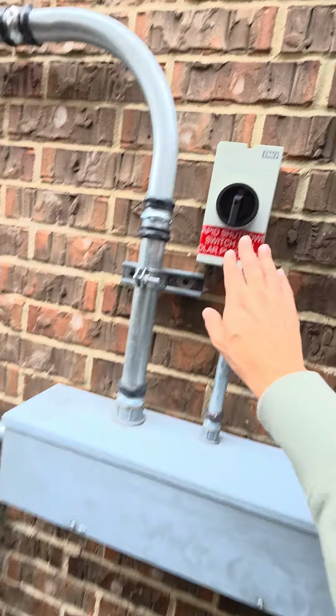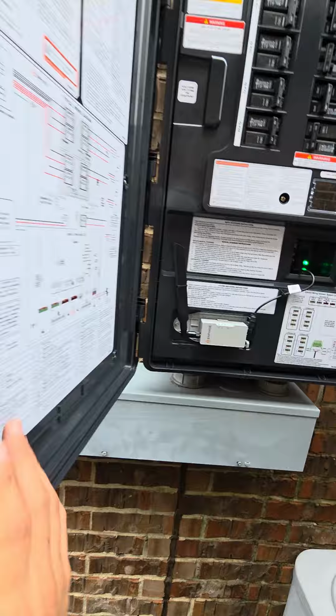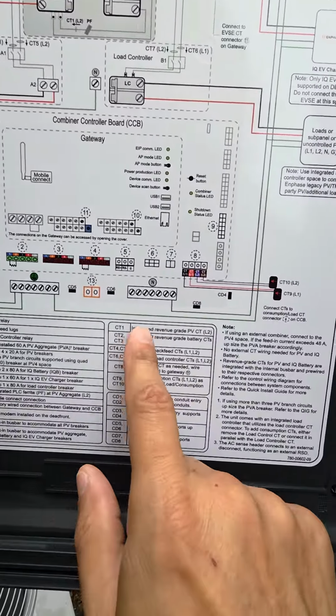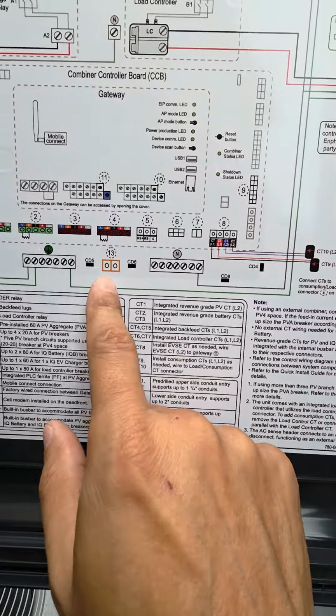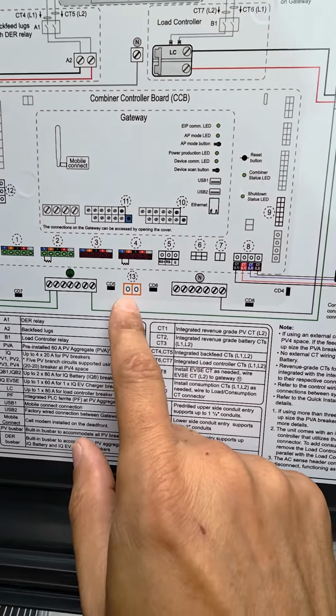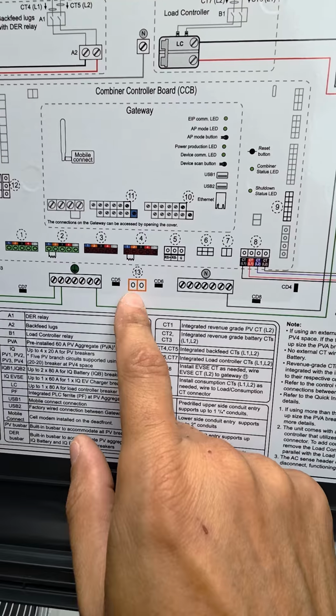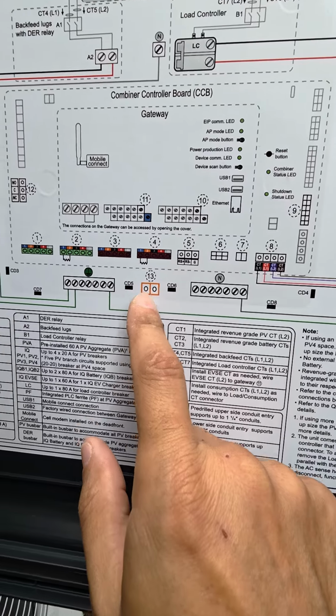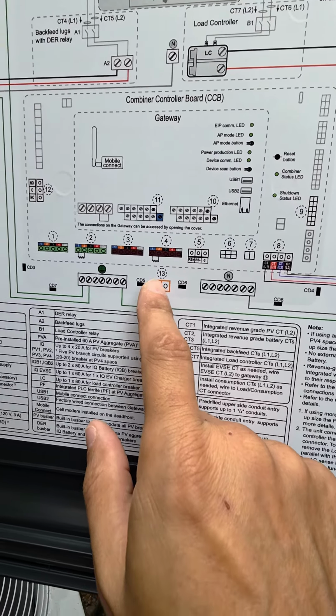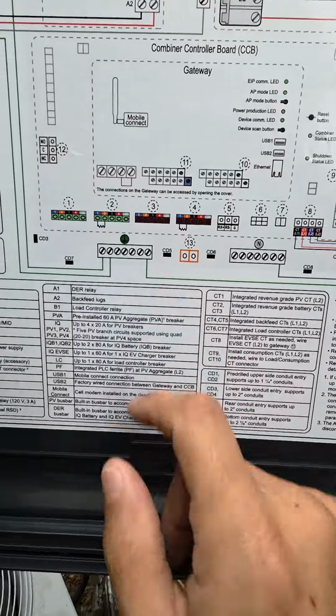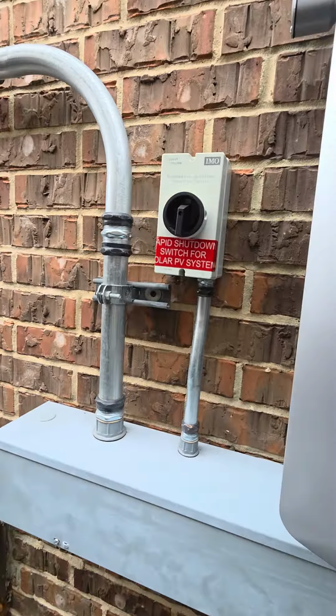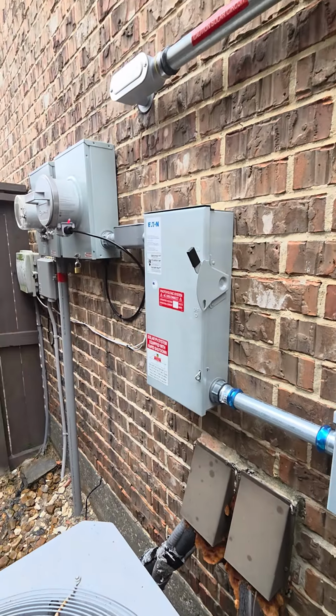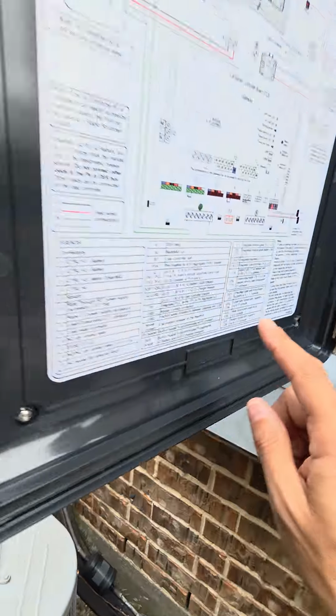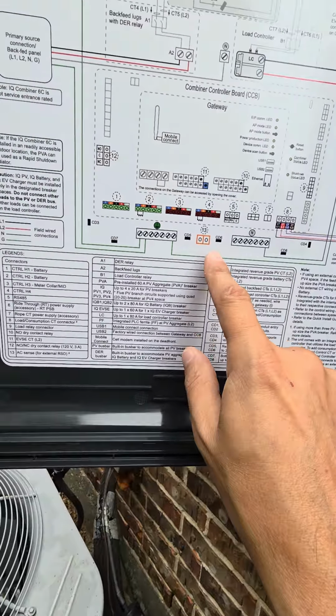So this right here goes to the AC sense, let's see if I can find it, on number 13 here. Here's your AC sense, and basically it comes bridged together with a wire, and you can take that bridge off and wire in your rapid shutdown switch. Or if you utilize a 3-pole, the third pole would come to that AC sense on number 13 here.